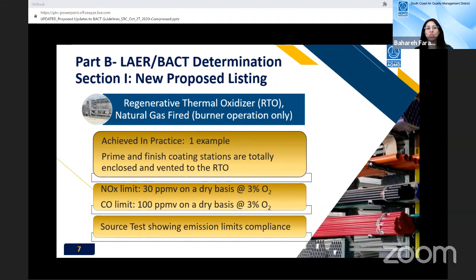This is just something I want to mention because it's in the form for additional information, but what we are doing here is establishing BACT for NOx and CO, not for VOC. It has been permitted at 30 ppm NOx and 100 ppm CO on a dry basis, corrected to 3% oxygen.